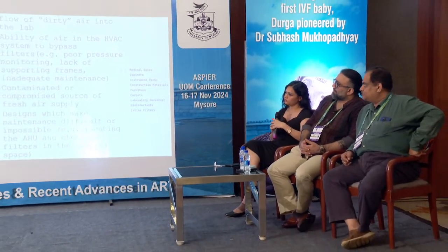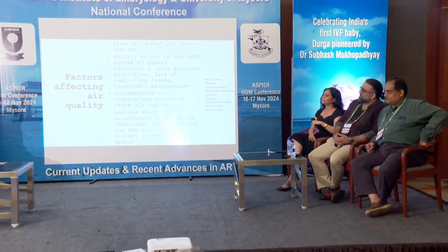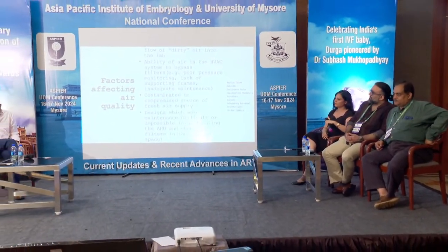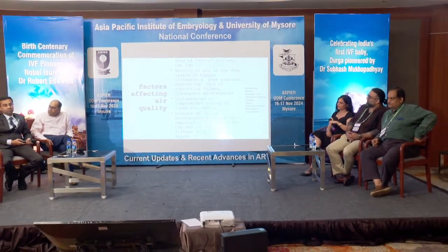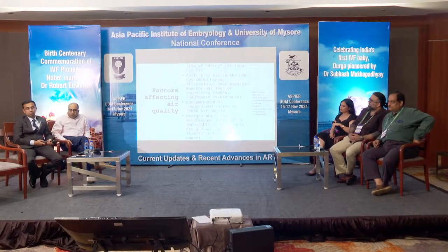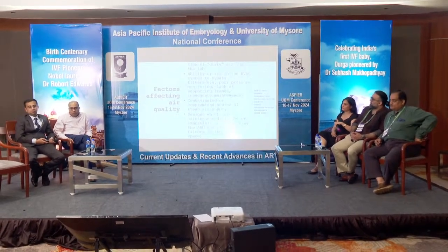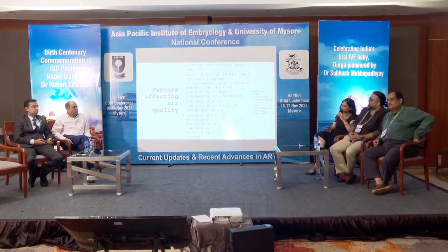The reason I'm insisting on that is that in almost 70% of labs, this kind of monitoring is outsourced. Meaning, before every batch, or maybe once in 3 months, an outsourced company would come with an equipment, measure all the parameters and go. Is that enough? No, ma'am, it has to be done every day, and any variation has to be addressed.